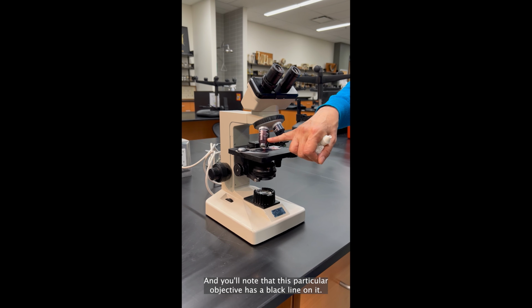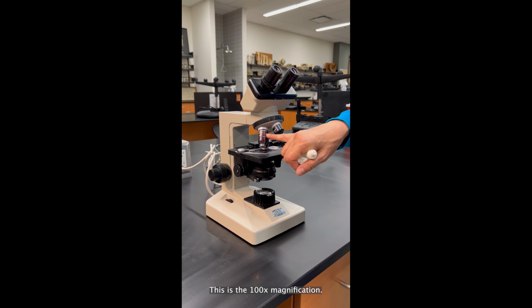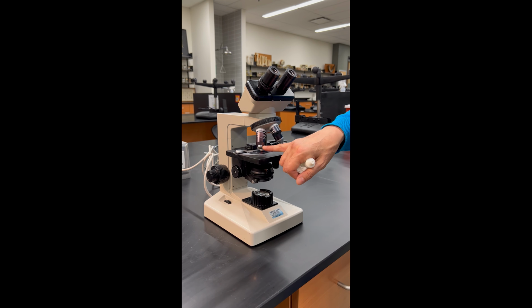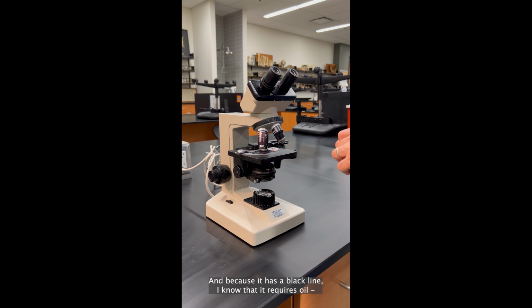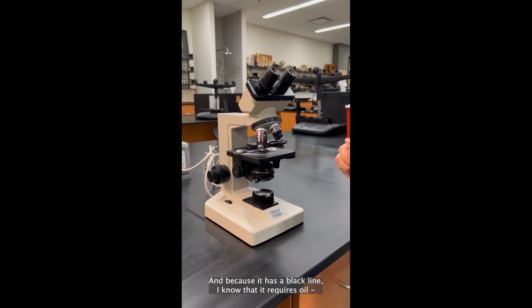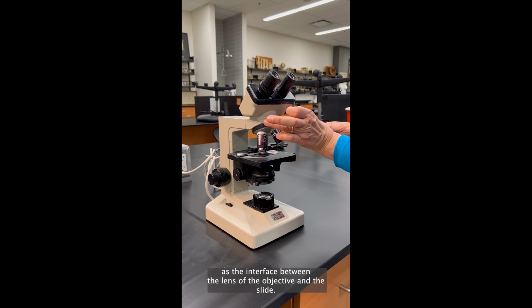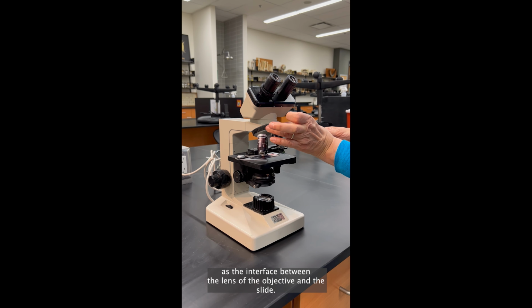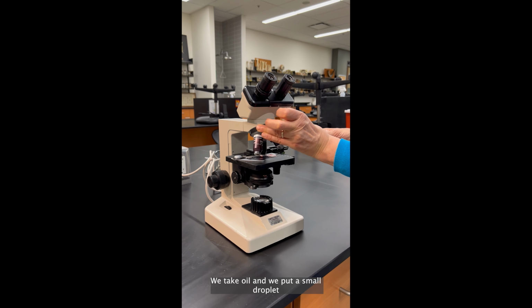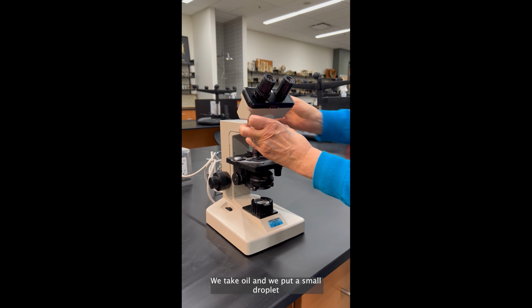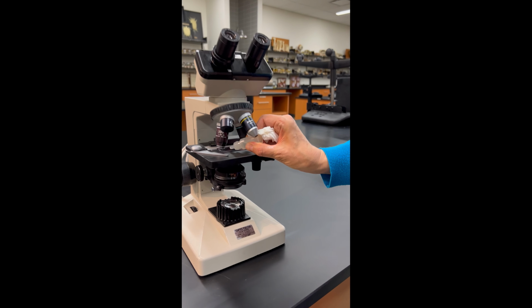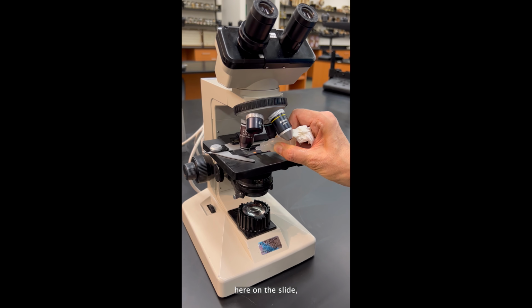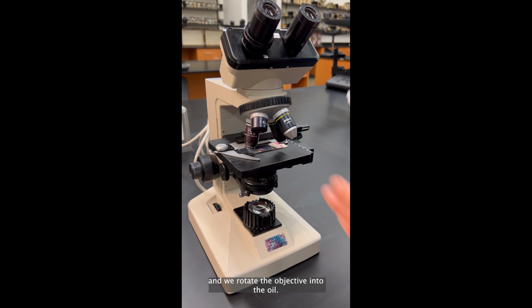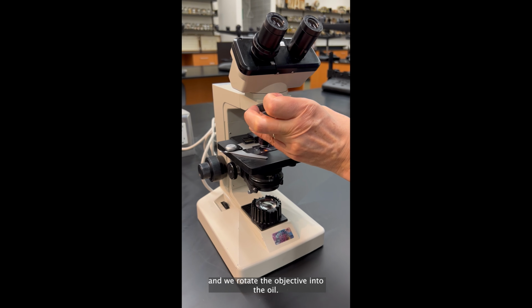You'll note that this particular objective has a black line on it. This is the 100 power magnification. Because it has a black line, I know that it requires oil as the interface between the lens of the objective and the slide. So we take oil and we put a small droplet here on the slide, and we rotate the objective into the oil.